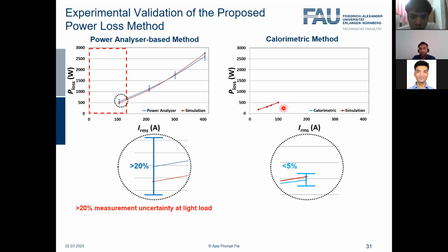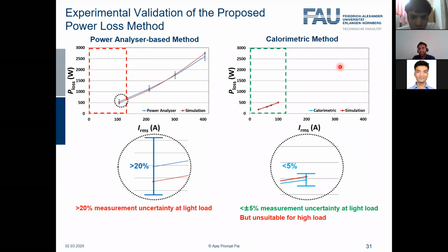Let me zoom in. So I'm taking once again the same point, the 100 ampere point. What we see here is the red or brown line is very close to the blue line, so the simulation matches the measurement quite well. But also the tolerance is now significantly lower - it's the same scale for the two bubbles here, and this is more or less 5%. So with the calorimetric method, we have a lower uncertainty at light load.